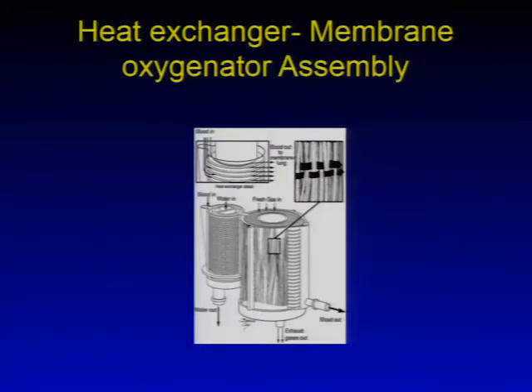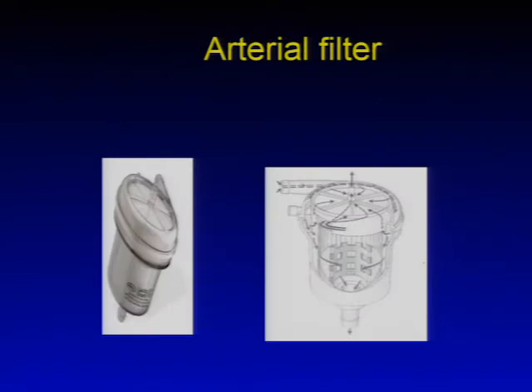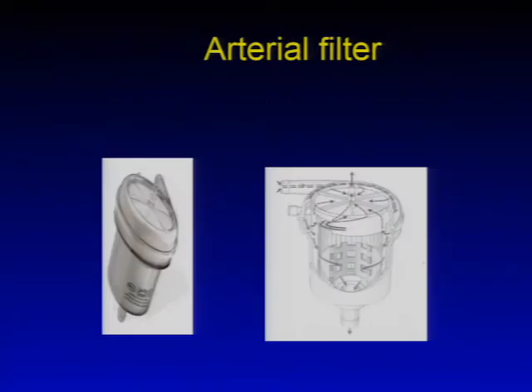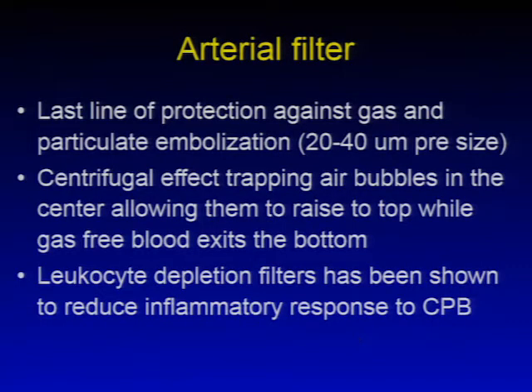After reaching the arterial line, blood passes through an arterial filter — the last line of protection against gas or particulate embolization. A centrifugal effect separates air or gas upward while blood is carried to the bottom. Leukocyte depletion filters have been shown to reduce the inflammatory response to CPB and are used in some centers.